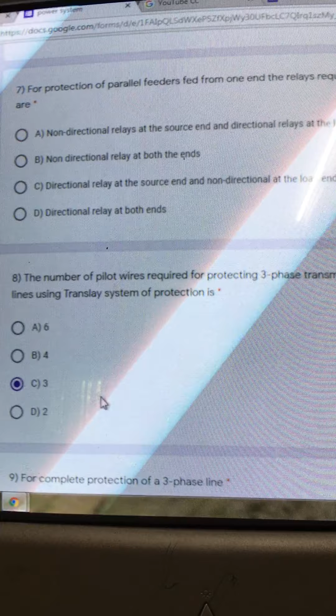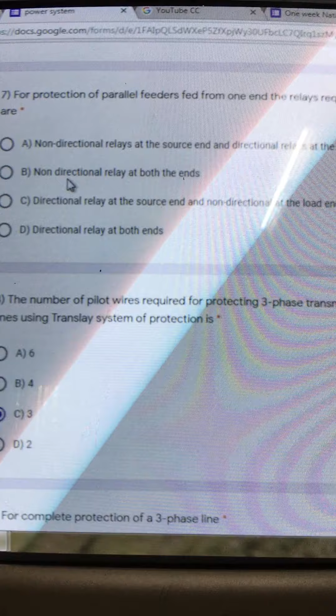Next question: for protection of parallel feeders fed from one end, the relays required are: option A non-directional relay at source end and directional relay at load end; option B non-directional relay at both ends; option C directional relay at source end and non-directional at load end; option D directional relay at both ends.